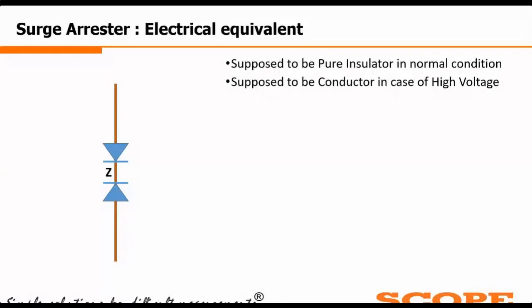So as I was telling earlier, a surge arrestor is supposed to be a pure insulator in the normal condition, and it is supposed to be a conductor in case of a high voltage beyond the rated voltage. So we can consider the construction of the LA as a single line diagram like this, with diodes in a back to back configuration. When the high voltage is there, it will conduct. In the normal condition, it will not be conducting.